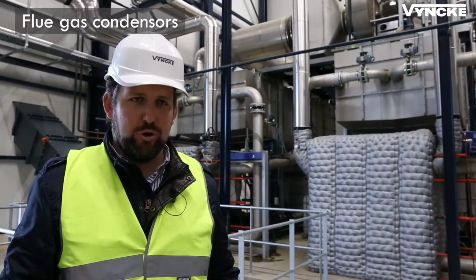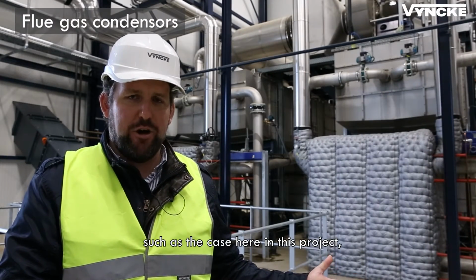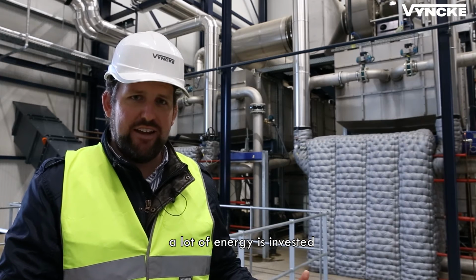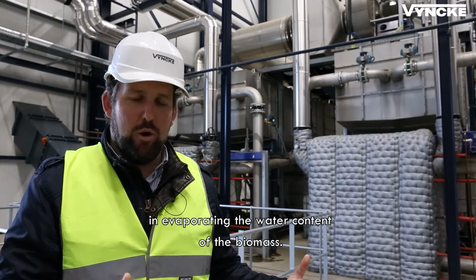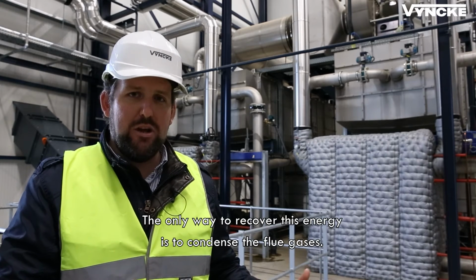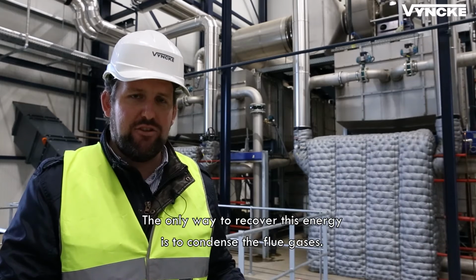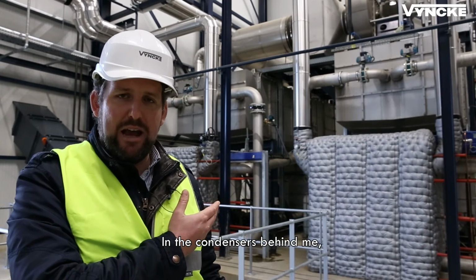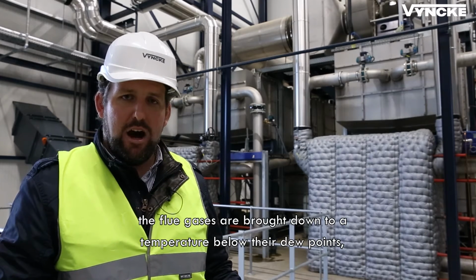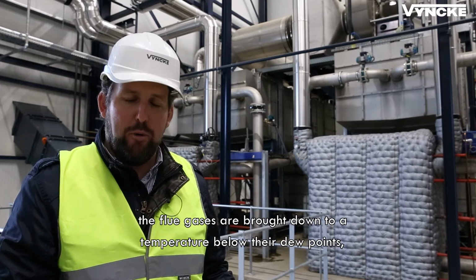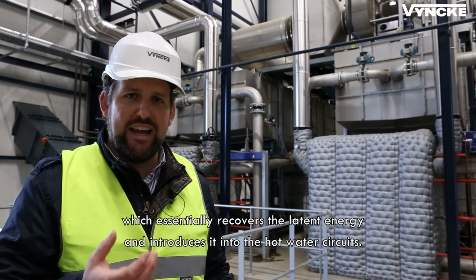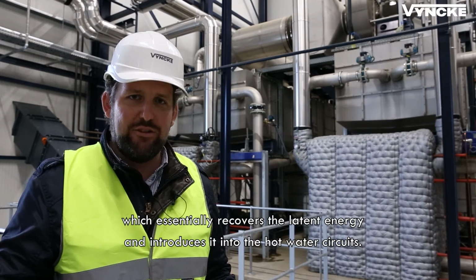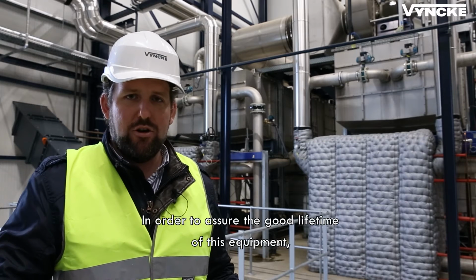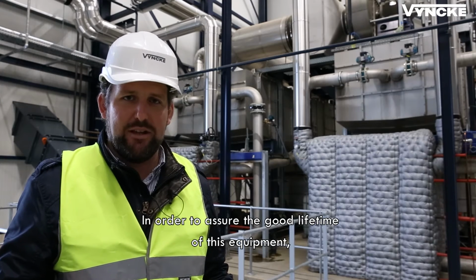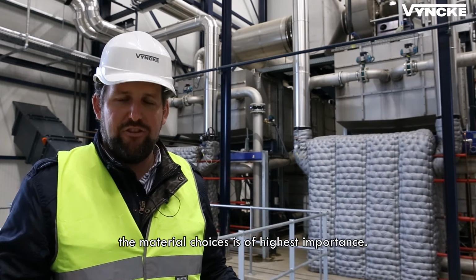When burning wet fuels, such as the case here in this project, a lot of energy is invested in evaporating the water content of the biomass. The only way to recover this energy is to condense the flue gases. In the condensers behind me, the flue gases are brought down to a temperature below their dew points, which essentially recovers the latent energy and introduces it into the hot water circuit. In order to assure the good lifetime of this equipment, the material choice is of highest importance.